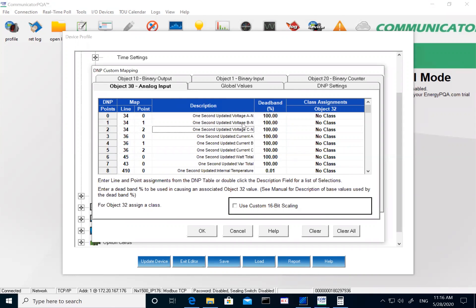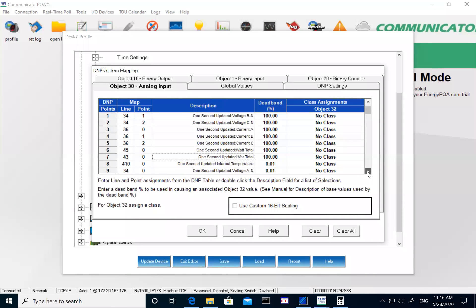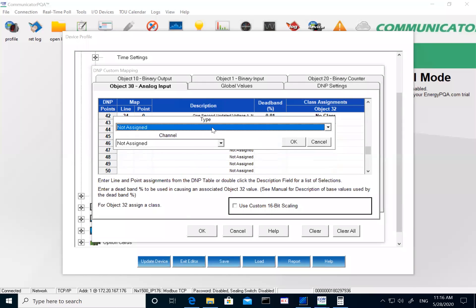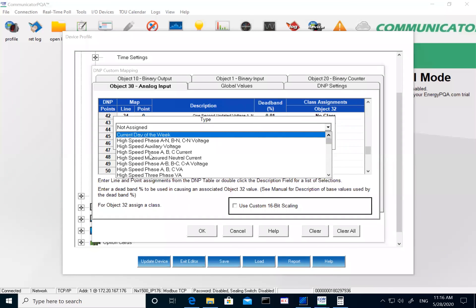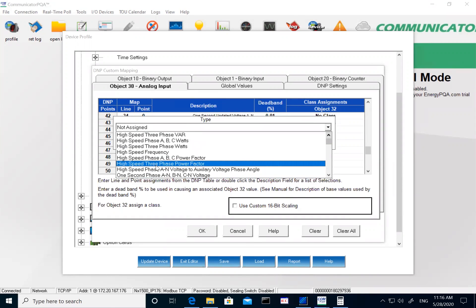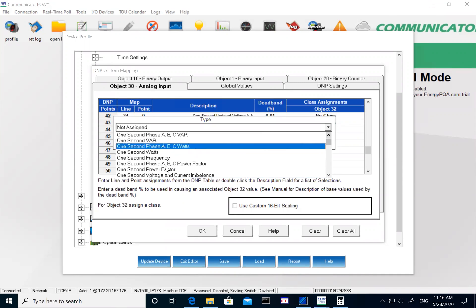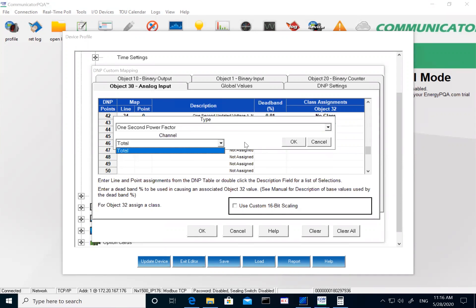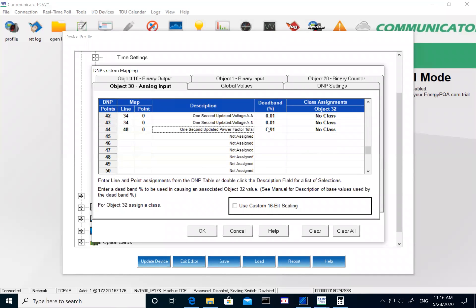I have set up voltage line-to-neutral, current, watts, and temperature. For any parameters you want to add, just pick an unassigned slot, double-click it, and it gives you a list of meter recordings. For example, to add power factor, I'll pick one-second readings, then select power factor total, and click OK. Now on object 30, point 44, I have my power factor listed.